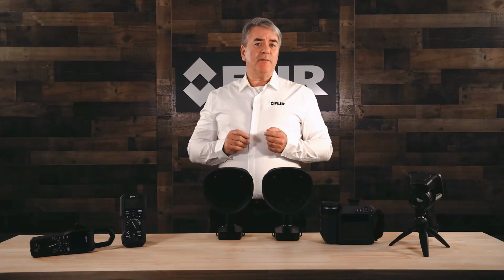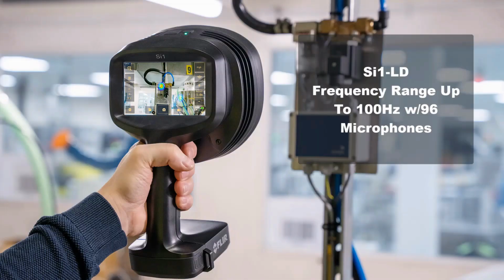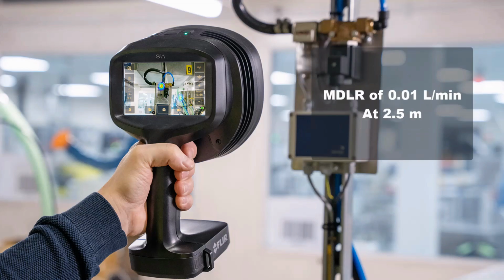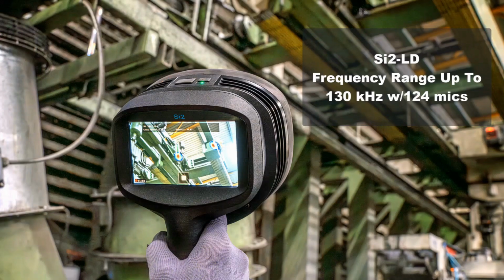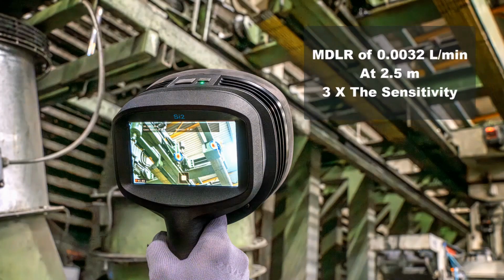Well, there are some performance differences. The Si1-LD has a frequency range of up to 100 kHz and has 96 microphones. This produces a minimum detectable leak rate of 0.01 liters per minute at 2.5 meters, or around 8 feet. Whereas the Si2-LD has a frequency range of up to 130 kHz and 124 mics. The resulting MDLR is 0.0032 liters per minute, which is around 3 times the sensitivity of the Si1.